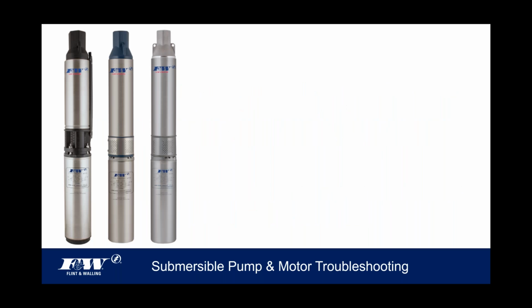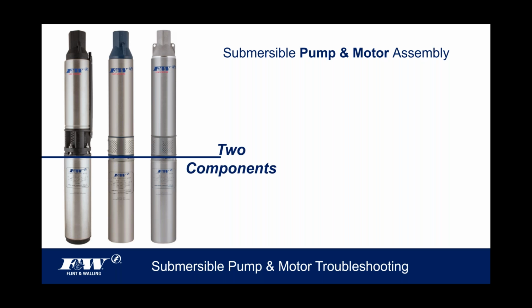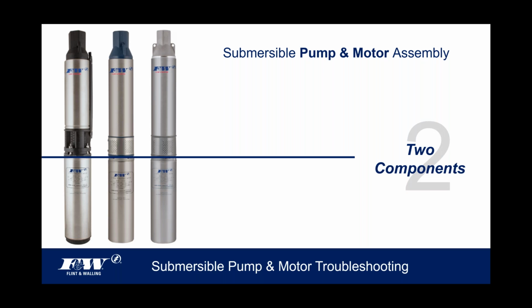When I look at pumps, whether they're submersibles, which is what we're going to be talking about today, or jet pumps or centrifugal pumps, really any type of pump that we manufacture, we call these submersible pumps, but from a troubleshooting perspective we might be better off referring to them as submersible pump and motor assemblies. In other words, I look at it as two entirely separate components that come together and make up a submersible pump and motor assembly.